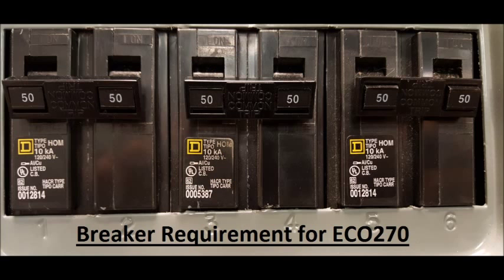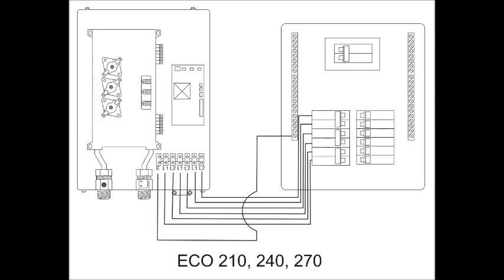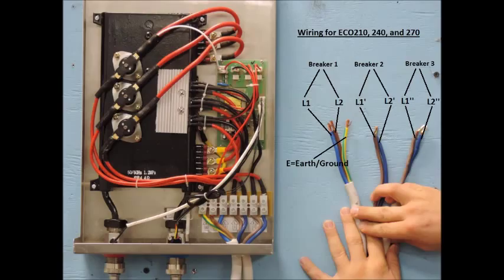Lastly, our ECO 270 unit runs on three 220 volt double pole 50 amp breakers, meaning the unit has access to 150 amps. This unit will wire up the same as the ECO 210 and 240, only it will be using a breaker with a higher amp limit.